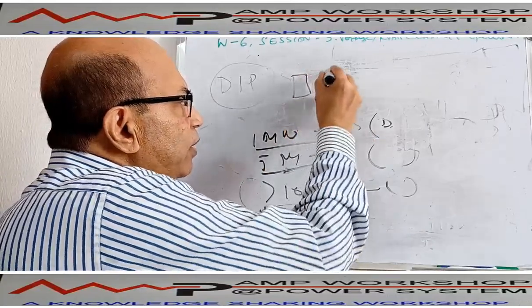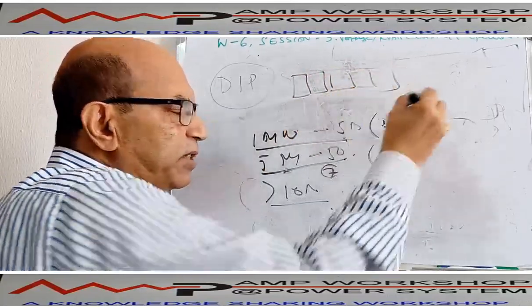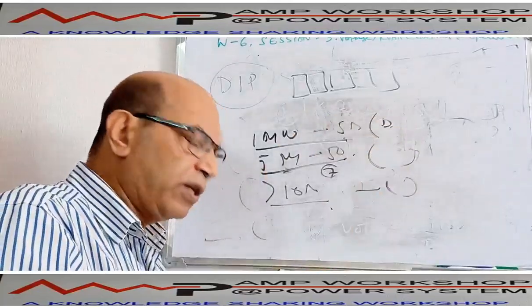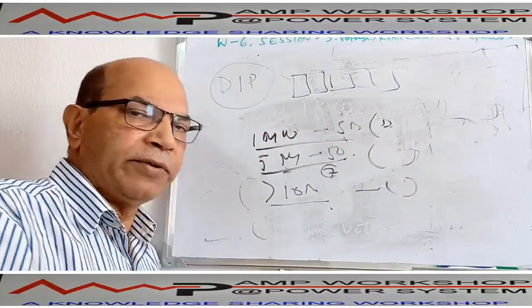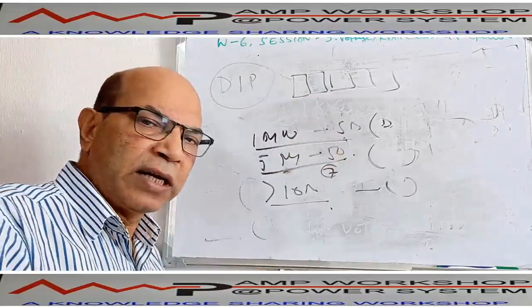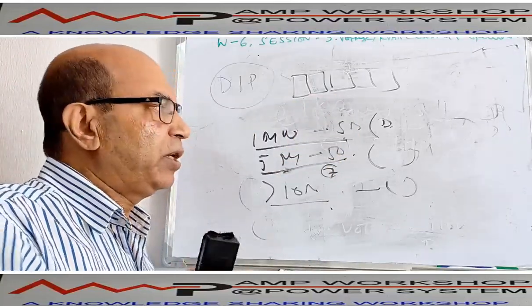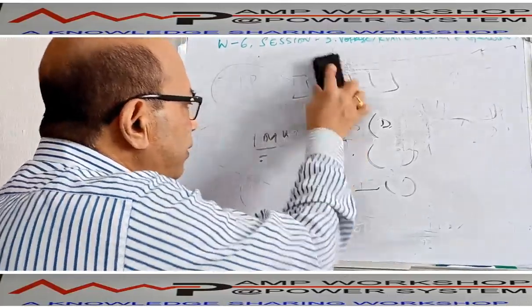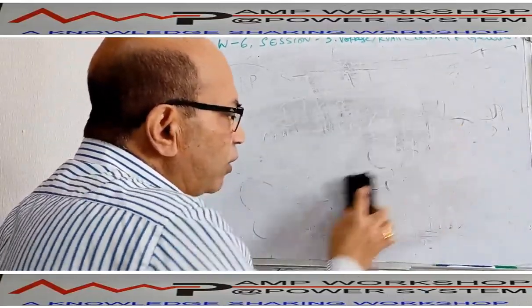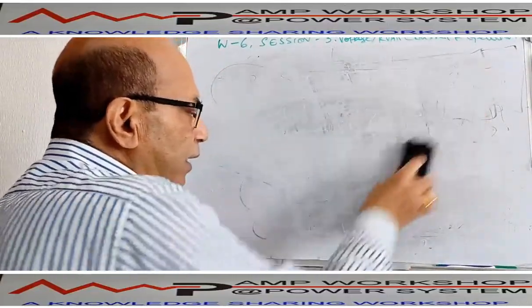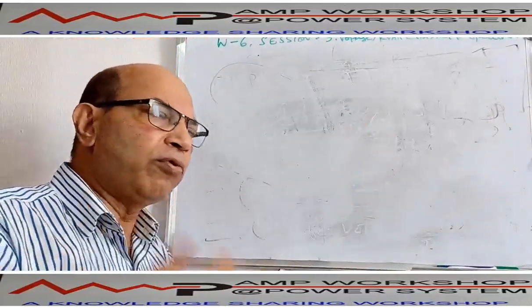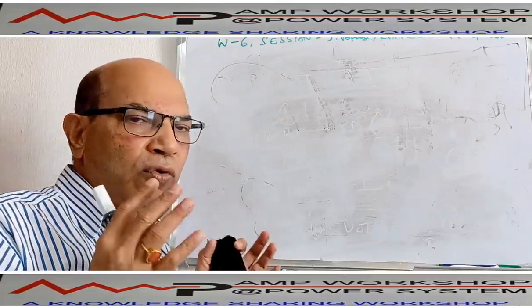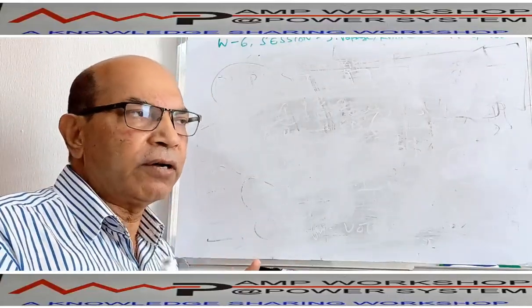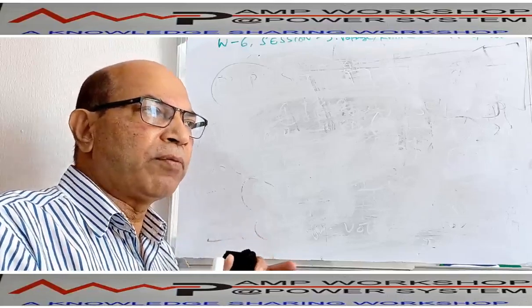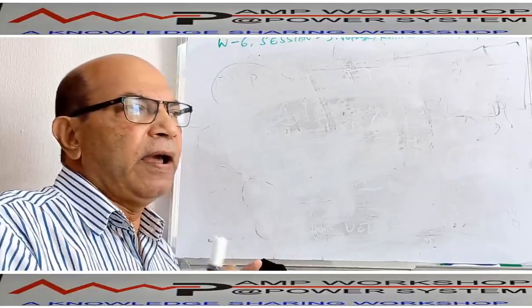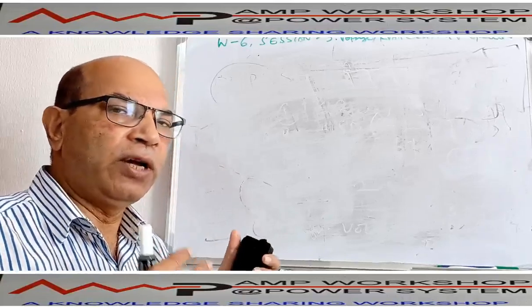So all these DIP switches you can see in one place, all the switches are available. Maybe 6, 7, 8, with different ones for the different selections. These are also available. So these are the various switches, and the switch is to be selected as per your requirement during site commissioning. These are the various settings available on the DIP switch on the AVR, and this is all about the automatic voltage regulator, and it will control the voltage. So if you want generator control, then there are two operations. One is an AVR, another is a governor. Governor is controlling speed and frequency and corresponding active power, and AVR is controlling voltage and corresponding reactive power.